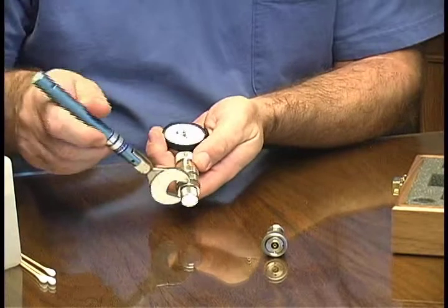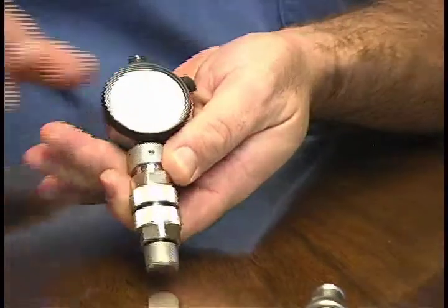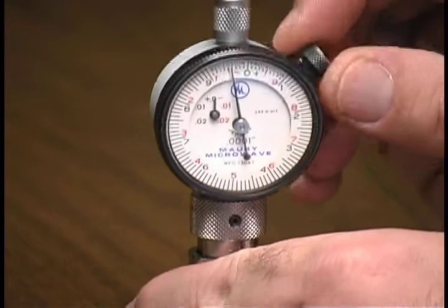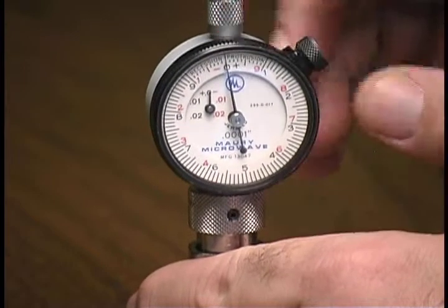To finish off, you'll want to torque it using the Maury torque wrench. Check the dial indicator to be sure it is zeroed. If not, loosen the locking nut and adjust the gauge ring to zero and relock the nut. This zeroes the gauge.